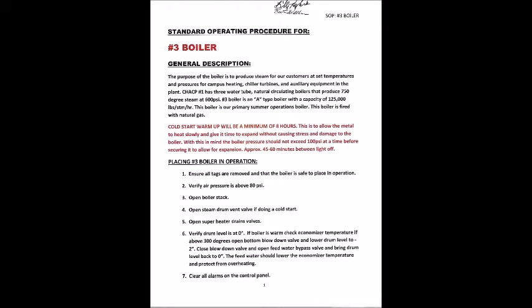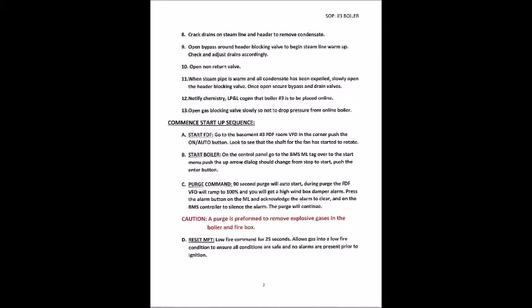If boiler is warm, check economizer temperature. If above 300 degrees, open bottom blowdown valve and lower drum level to minus 2 inches. Close blowdown valve and open feed water bypass valve and bring drum level back to 0 inches. The feed water should lower the economizer temperature and protect from overheating. Step 7. Clear all alarms on the control panel. Step 8. Crack drains on steam line and header to remove condensate.